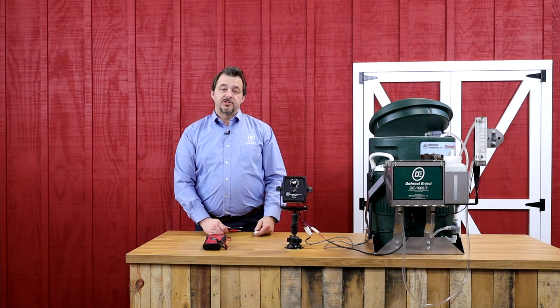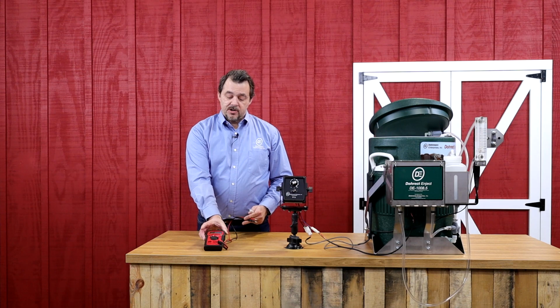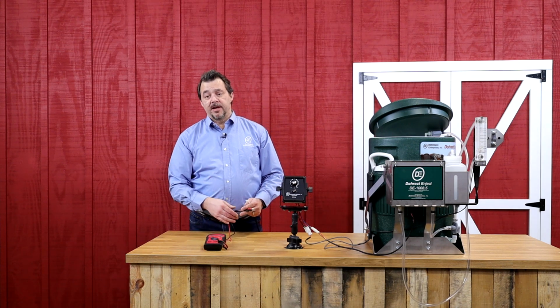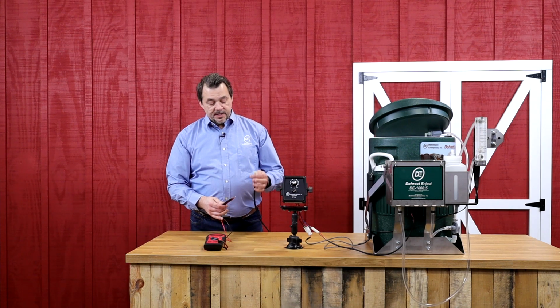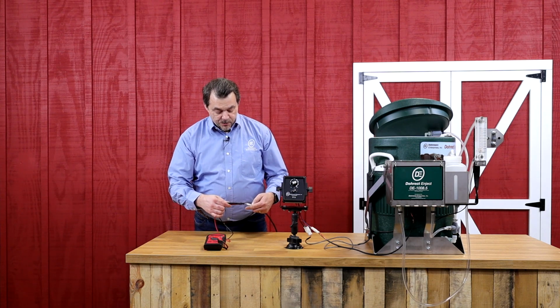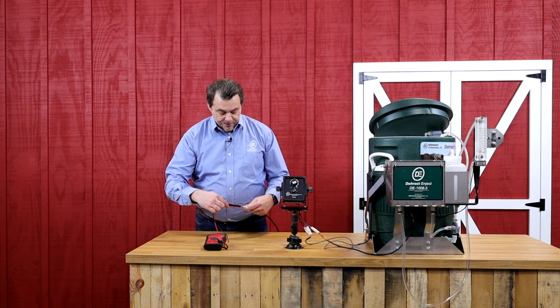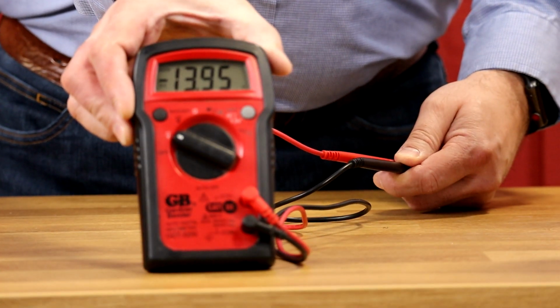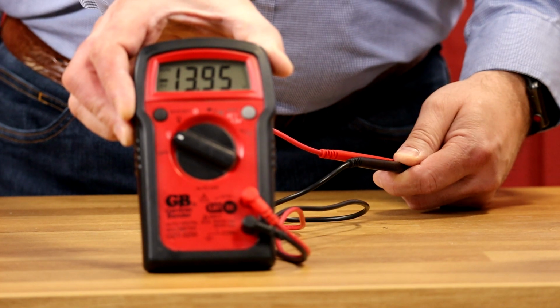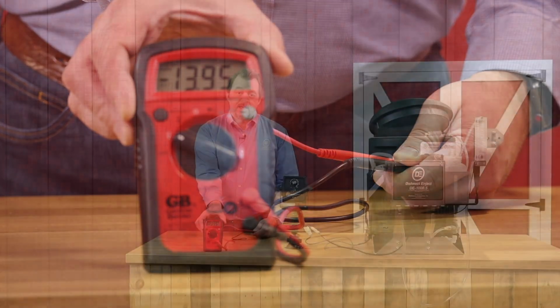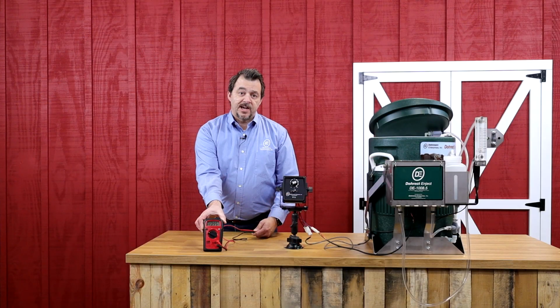Now, another thing that I mentioned is that with the multimeter, we have the ability to see the polarity. So when we test this, if we go red to red and black to black, what you will see on the display now is that we have a negative number. So this is reading negative voltage, and what that means is that our power wire is actually hooked up to ground, and our ground wire is actually hooked up to power.